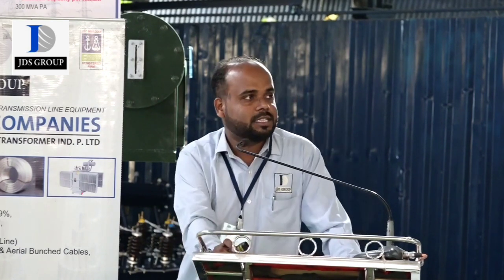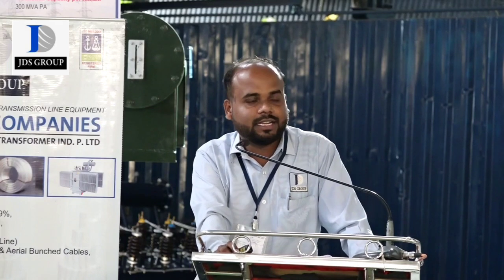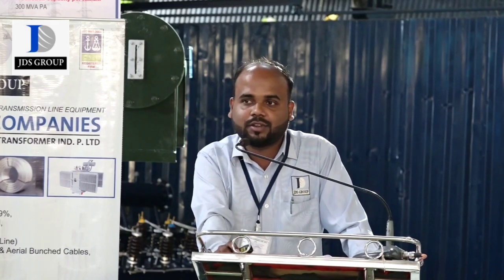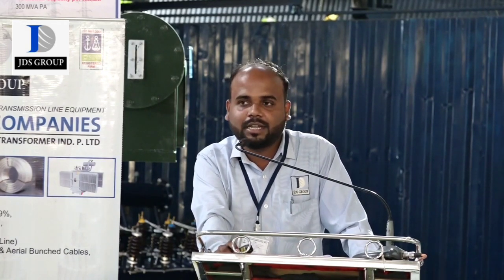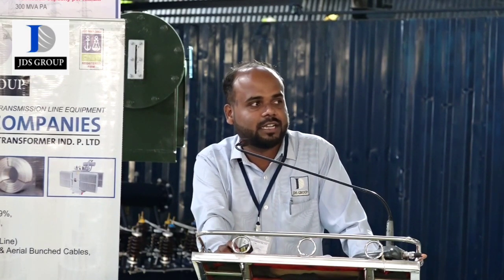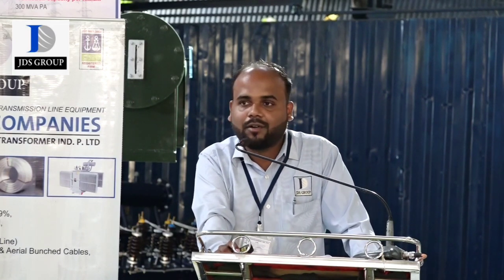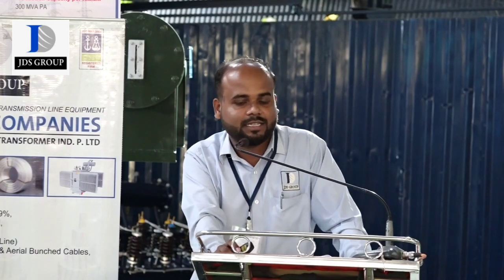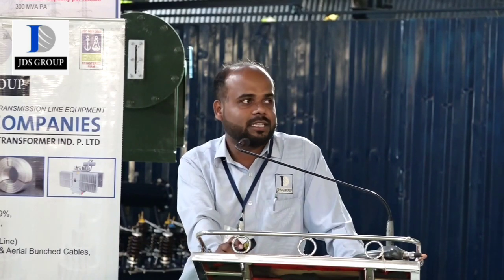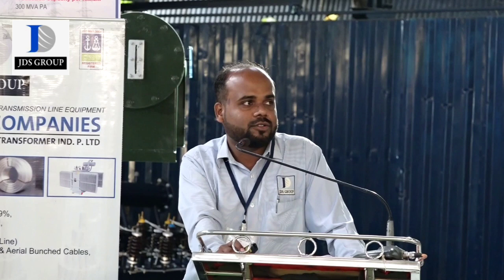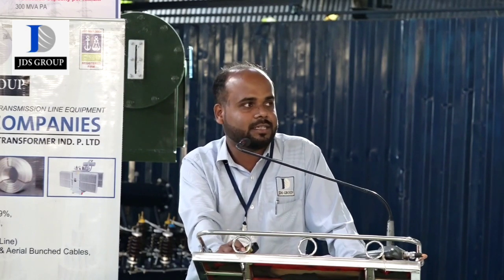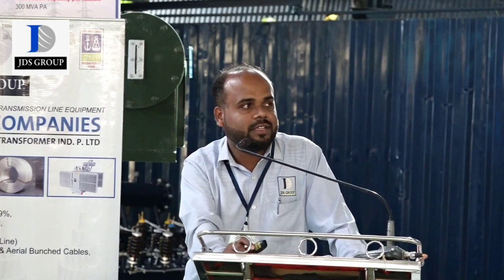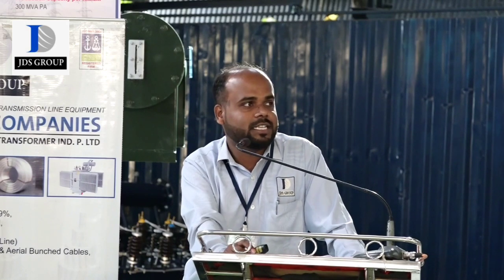So the first test is the winding resistance test. The winding resistance test is performed to check the resistance of the transformer. This is done with the help of a digital resistance meter. For a power transformer, we use a 10 ampere digital resistance meter. We calculate the resistance at ambient temperature and also convert it to 20 degrees Celsius. HV resistance has been measured in ohms and LV resistance has been measured in milliohms.